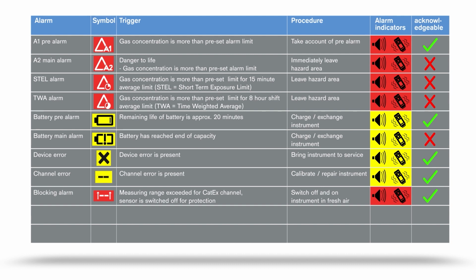There is one exception to this. For methane, the Cat-X sensor offers the option of automatic range switchover within the range of 0 to 100 volume%. In this case, there is no blocking alarm. This option is only available with the X-am 8000. An over-range alarm is triggered when the measuring range has been exceeded. The ambient air contains concentrations that exceed the measuring range of the sensor concerned. Leave the hazard area immediately.